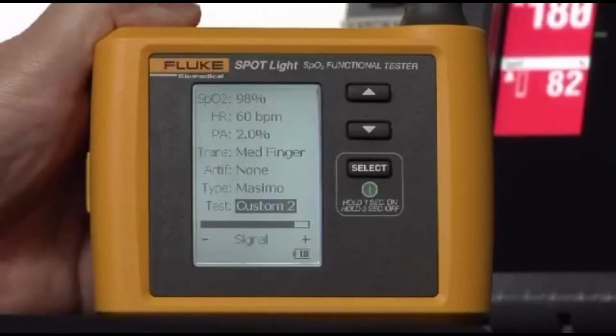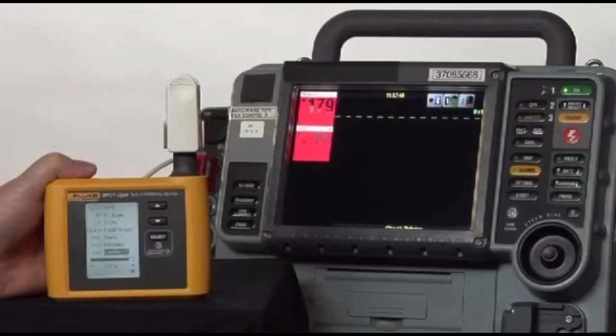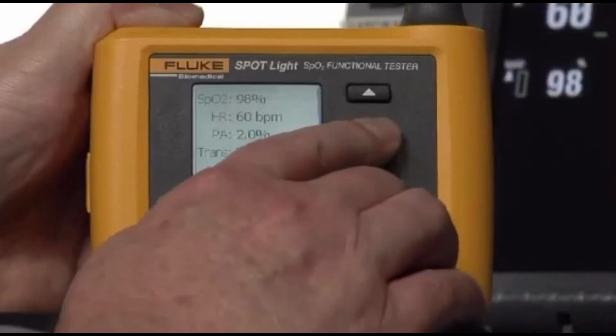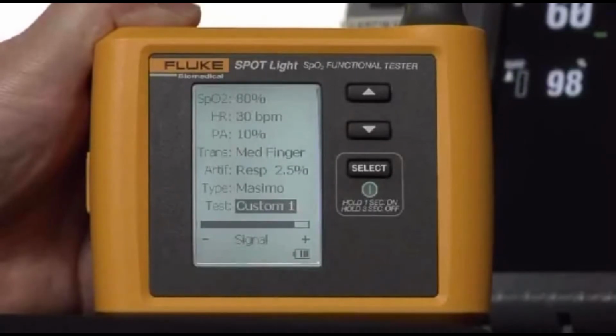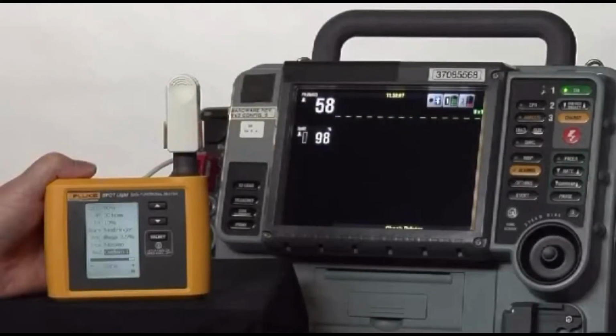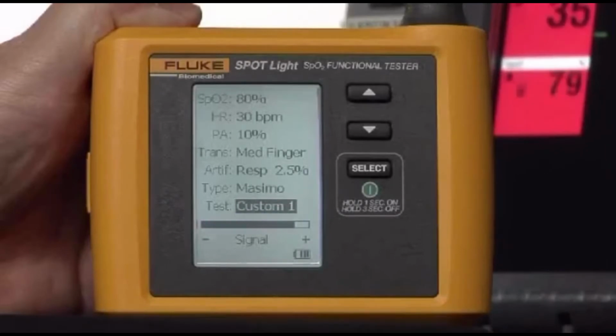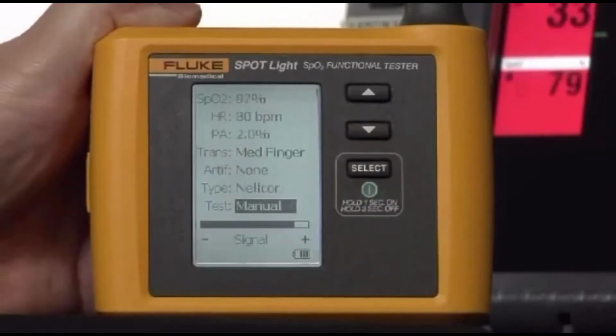We want to let the alarms continue to sound because the normal conditions will let them silence on their own, an important part of the functional test. Again, waiting for those to settle, and then we'll simply push one more time for our hypotensive patient with a low O2 saturation, low perfusion. And you'll see the alarms will sound again, this time on the low end. And again, we'll wait for the readings to settle. And we'll push one more time to get back to a more normal reading so the alarms will quiet once more.